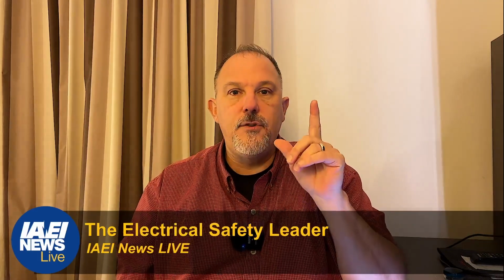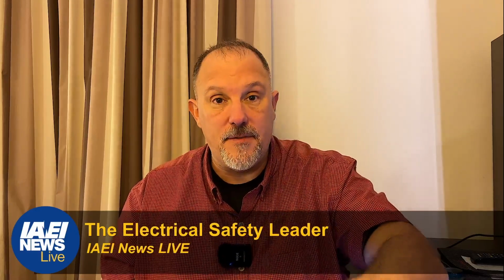You have to make sure that when you turn the breaker off, you turn both of those off, because both branch circuits land on the same device. We don't want someone to turn one breaker off and end up having an energized part out there.